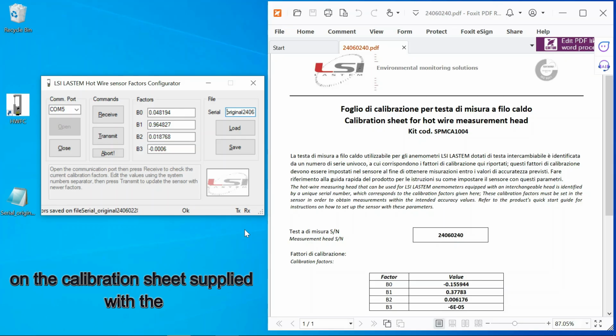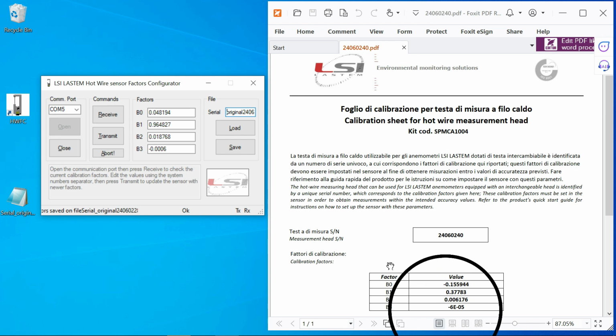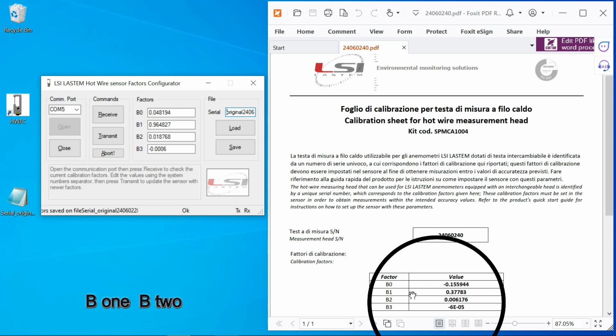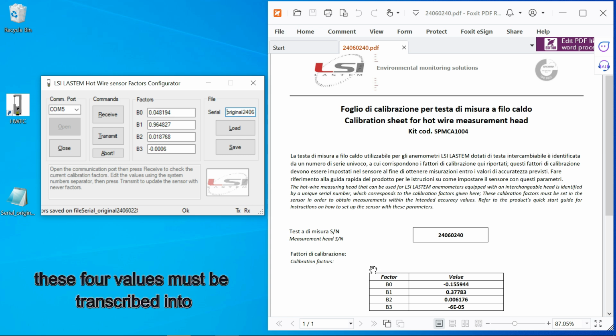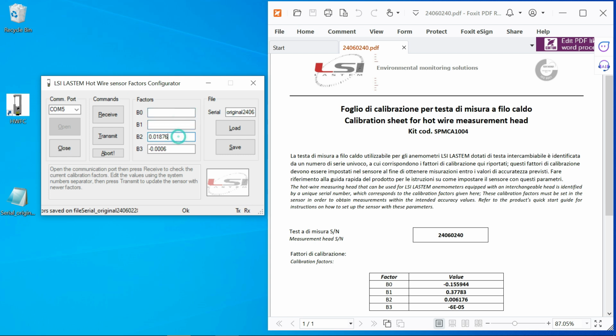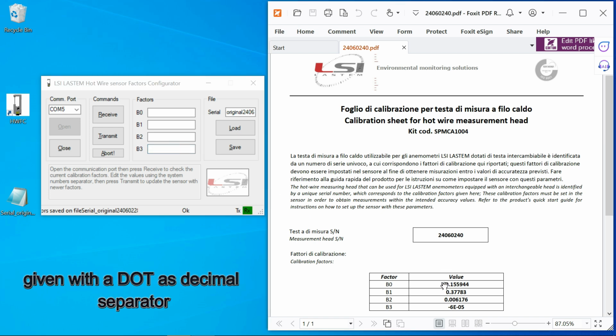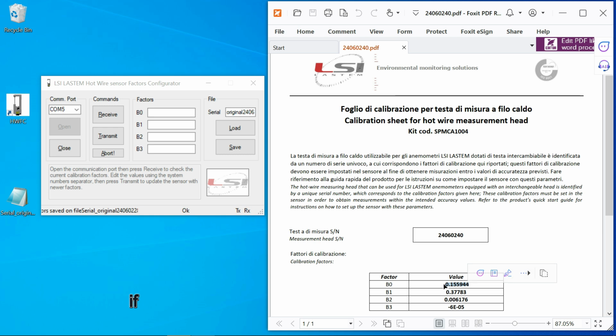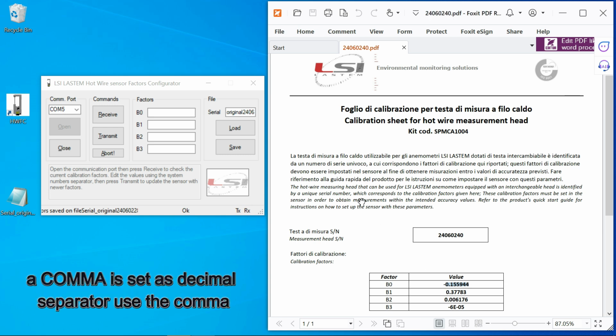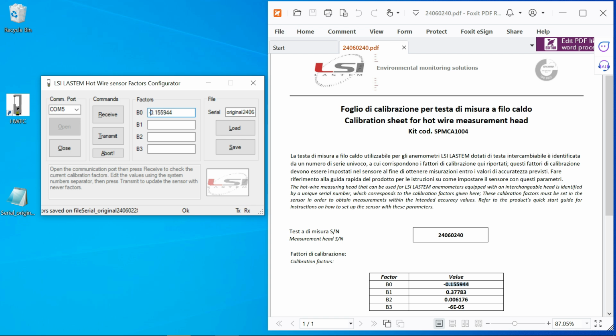On the calibration sheet supplied with the new head, the factors B0, B1, B2, and B3 are given. These 4 values must be transcribed into the 4 boxes, replacing the values currently shown. Attention! On the calibration sheet the values are given with a dot as decimal separator. If, on your PC, a comma is set as decimal separator, use the comma instead of the dot.